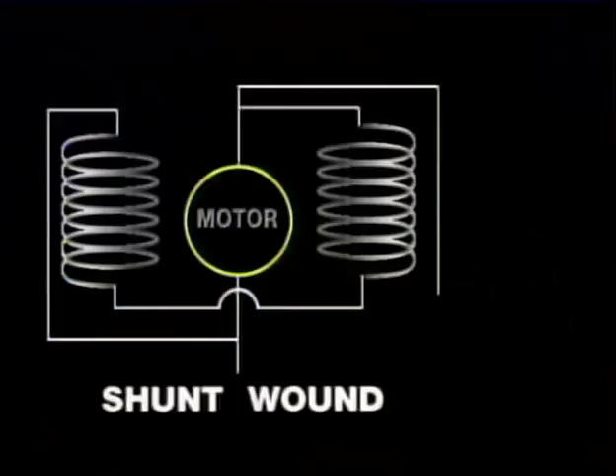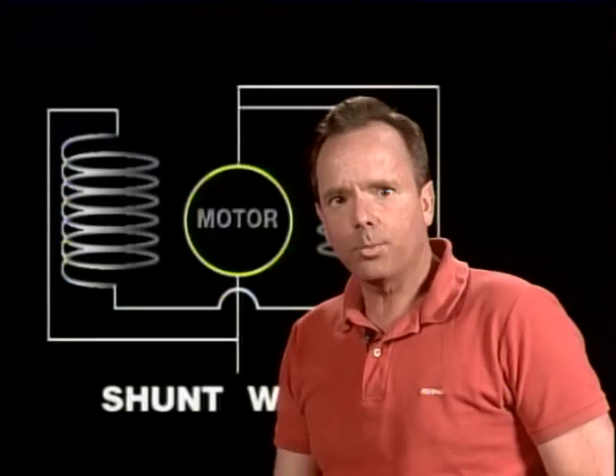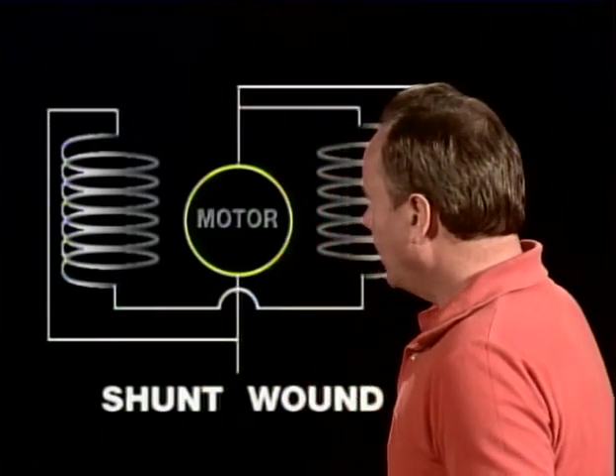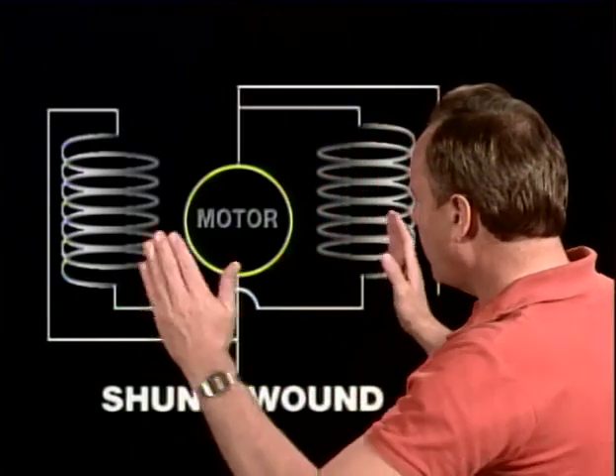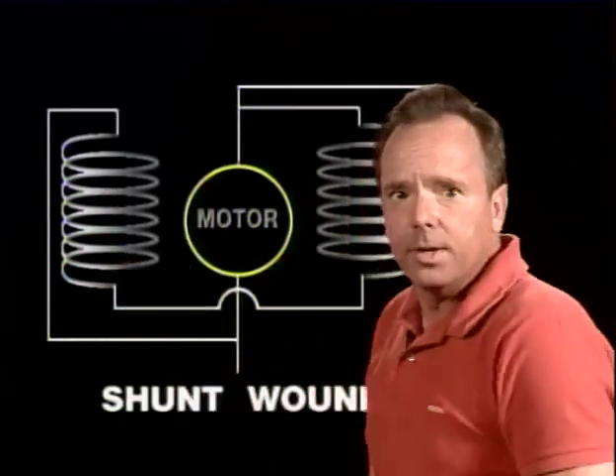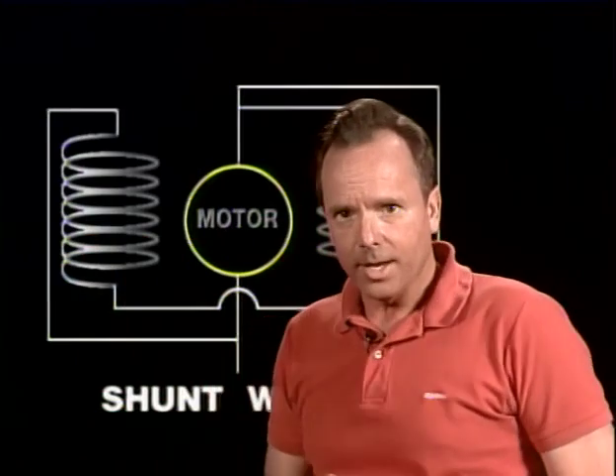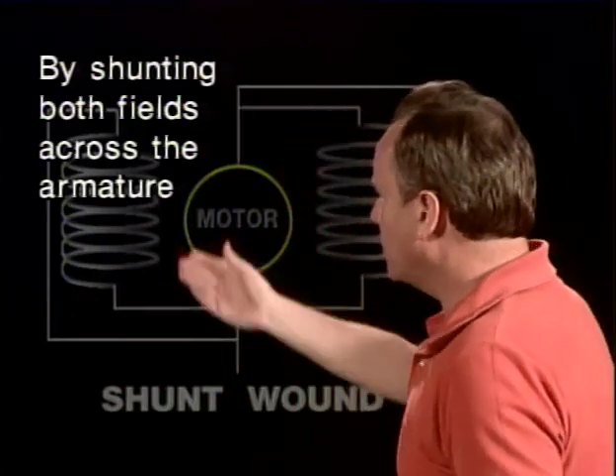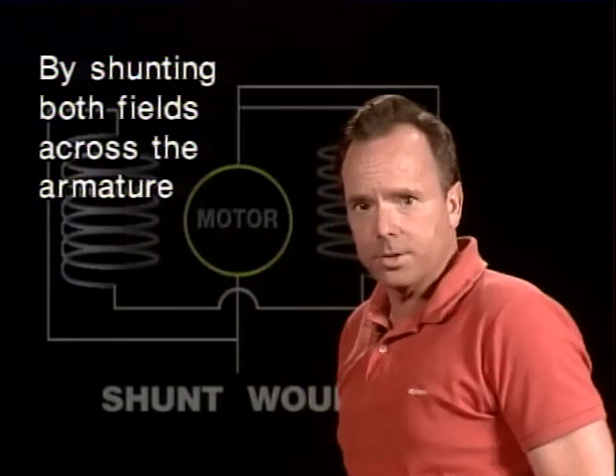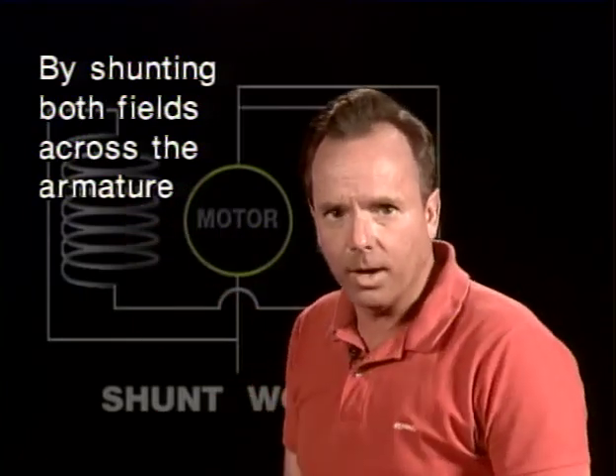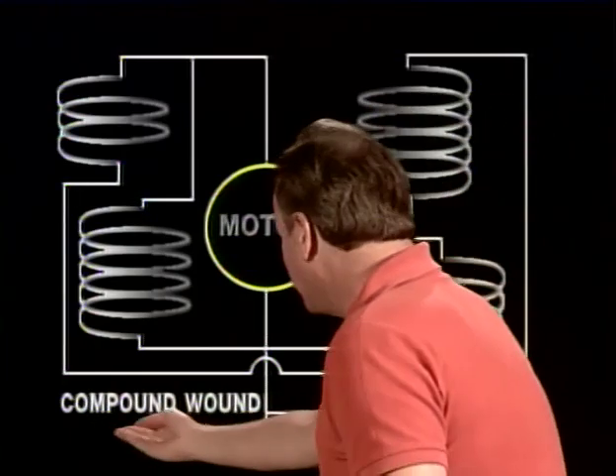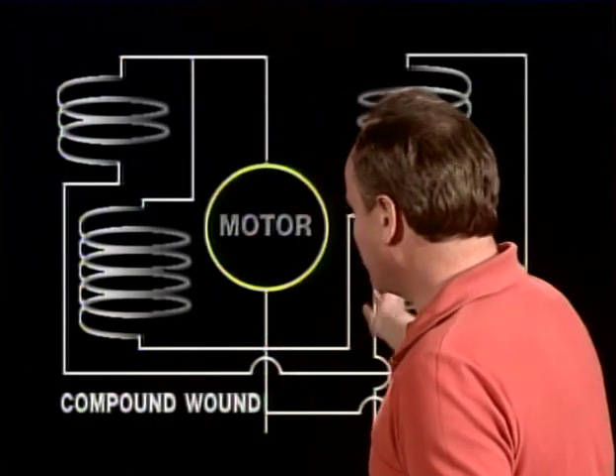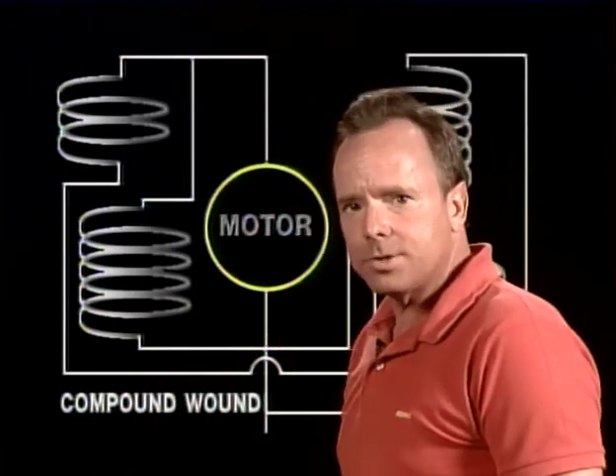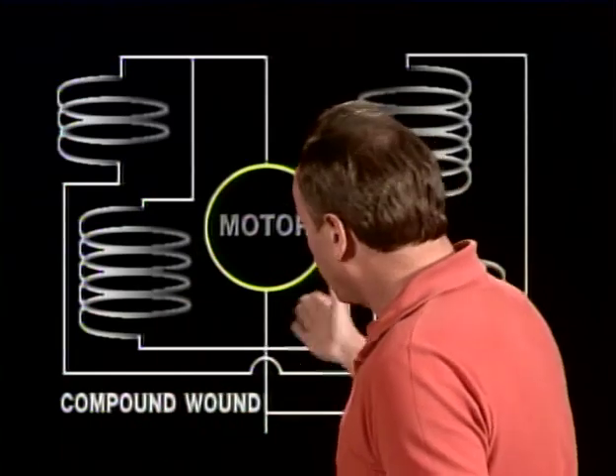Now, another way generators and motors can be wound is shunt wound. Shunt wound is, instead of series, parallel. What that means is the current flows in parallel between the armature and the fields. So a shunt wound DC generator, they're going to ask you in the test, is connected how? Well, it's connected by shunting both fields across the armature. Instead of being in series, it's parallel. That's called shunt wound. Now, the last winding design we need to talk about is compound wound, and you can see it's complicated if nothing else. It's a combination series wound and shunt wound winding, and they're only going to ask you one question about this on the test, and it has to do with regulating the voltage output of a compound wound DC generator.